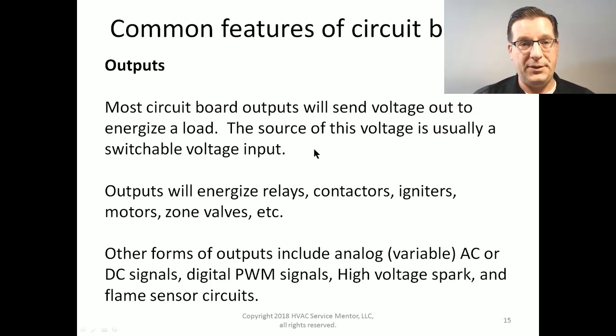Let's look into outputs. Most circuit board outputs will send voltage out to energize a load. And the source of this voltage is usually a switchable voltage input, which we've already talked about. Outputs will energize relays, contactors, igniters, fan motors, valves, dampers, etc. Other forms of outputs include analog outputs, such as a variable AC or DC signal, and a digital pulse width modulating signal, and we're seeing more pulse width modulating on variable speed blowers and compressors, more and more common. High voltage sparks and flame sensor circuits, these are analog outputs.